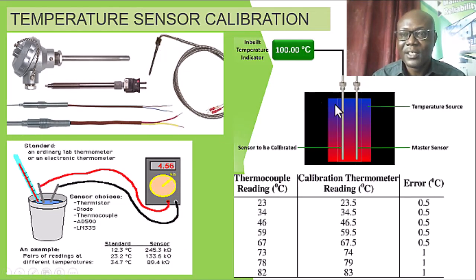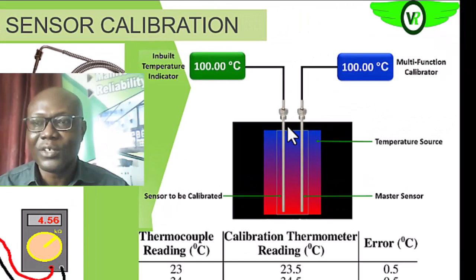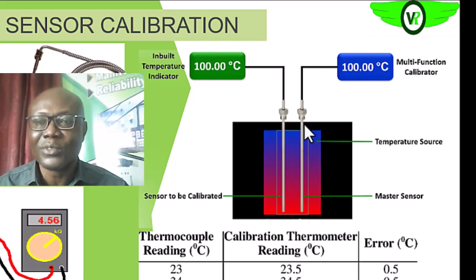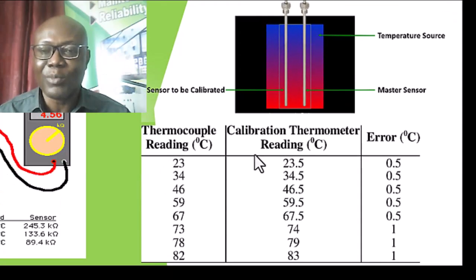So here we have the temperature indicator. Okay, then this is the calibrator. Are we getting it? So when we subject both of them to the same condition, as you can see here, we are supposed to have the same output. That is the output that will correspond to 100 degrees Celsius if we heat this to 100 degrees Celsius, which means that if the master meter is giving us 100 degrees, this is supposed to give us 100 degrees Celsius. Okay, so the thermocouple reading and the calibrator reading may be different, and we'll see the errors. So if they are within tolerable limits, they are acceptable.